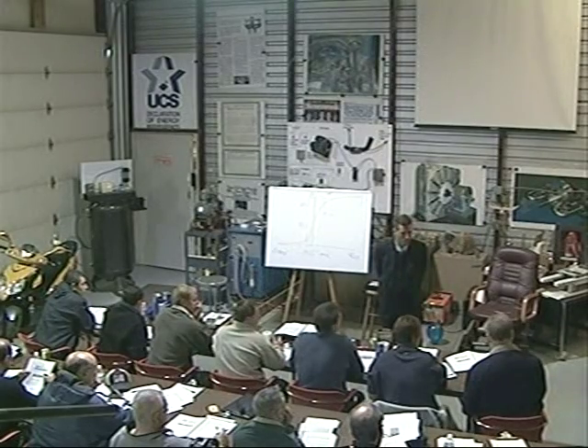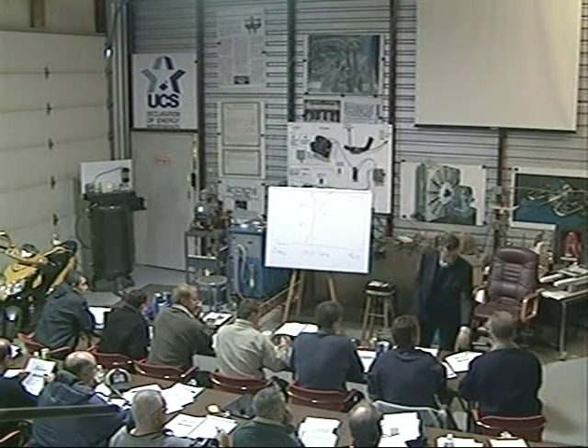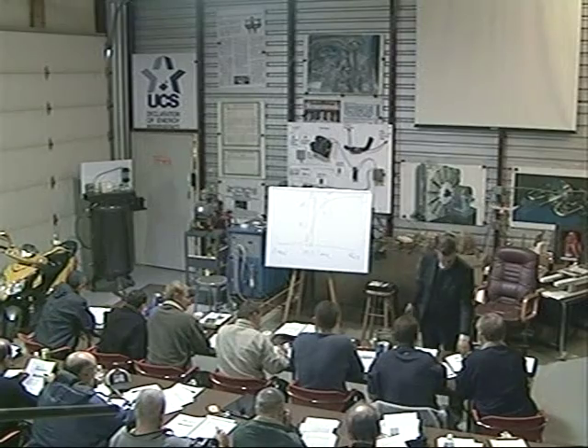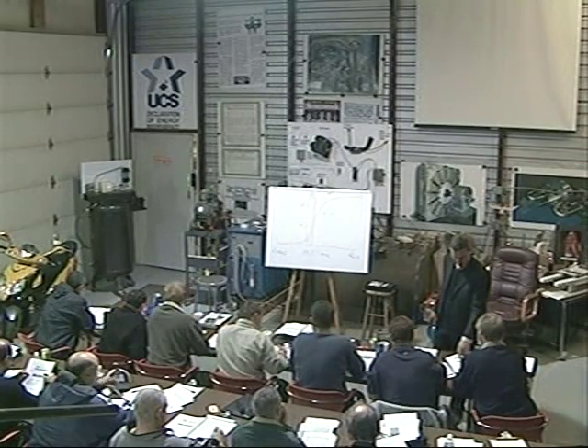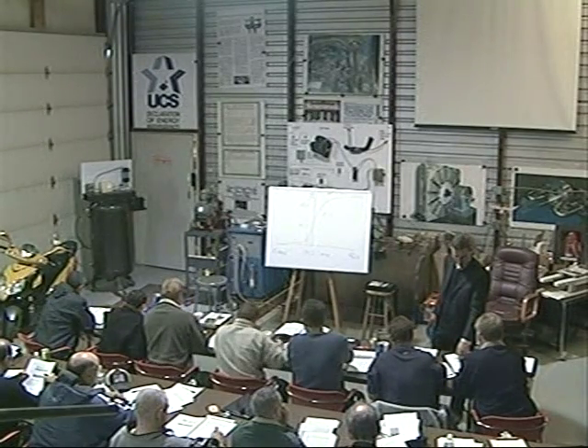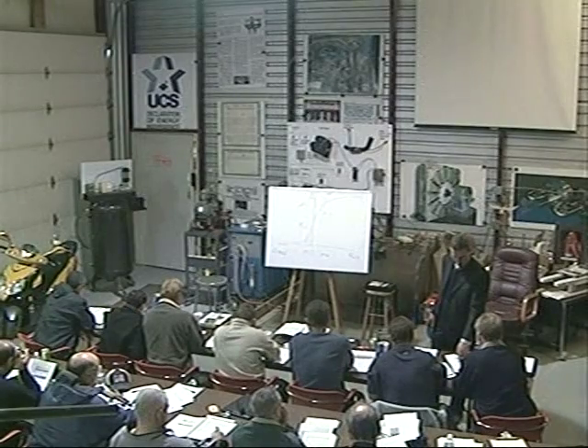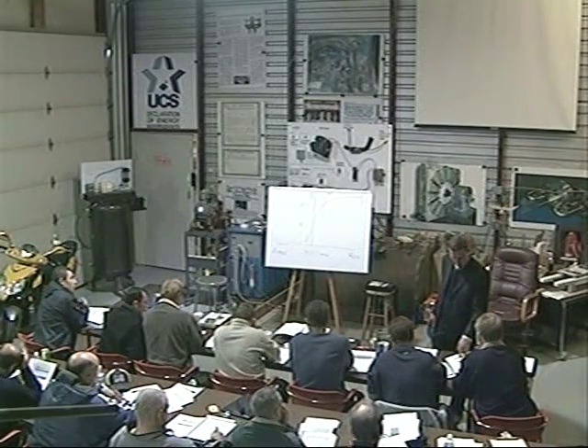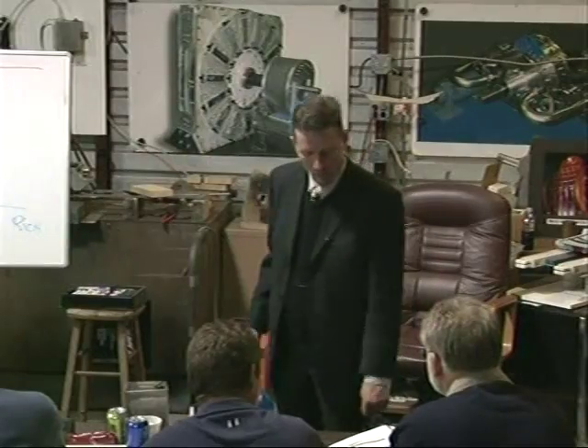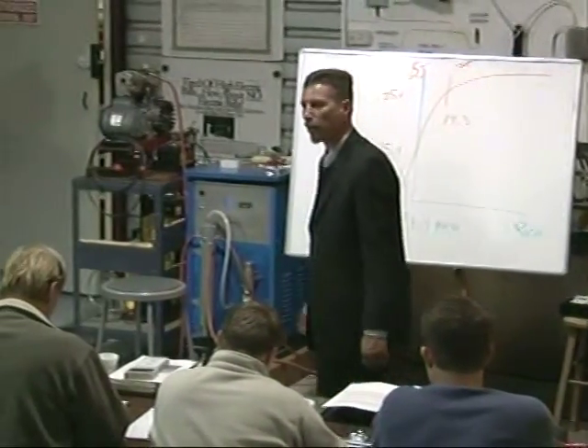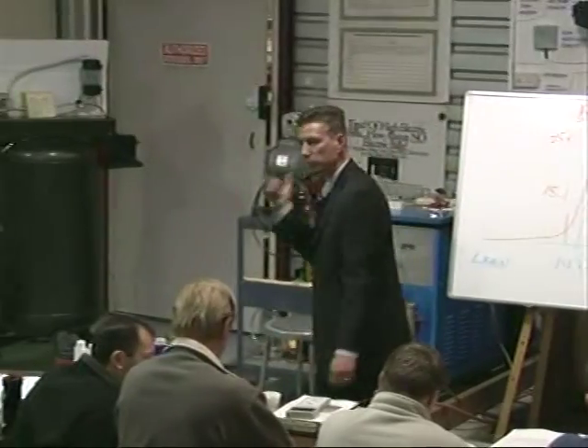We're changing it to 0.16 and 0.35. So our low signal is going to be 0.35 volts, our high signal will be 3/4 of a volt, 0.75. What's going to toggle that? Wherever we set our optimizer, it's set from the factory at 0.16 volts, and 0.16 volts is probably spot on for that Escort.